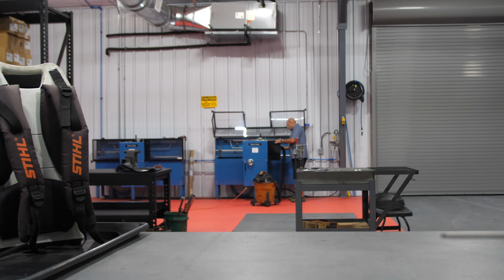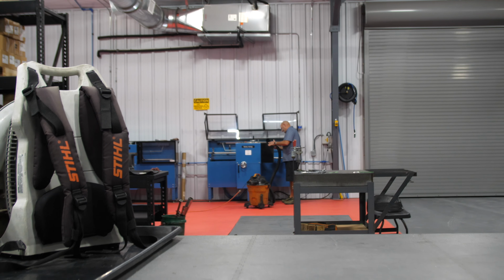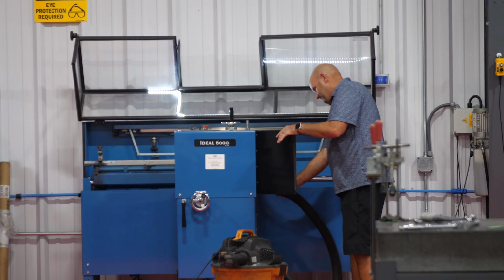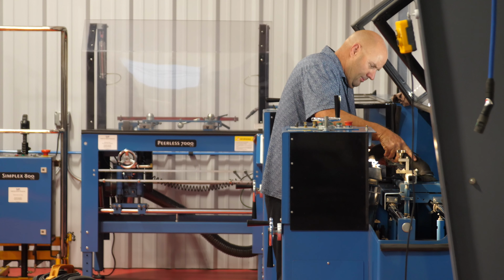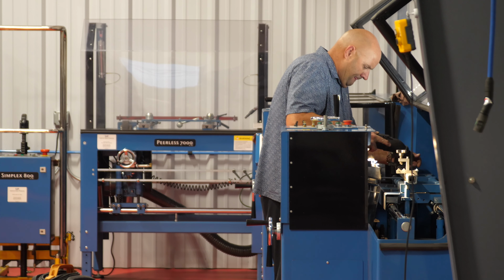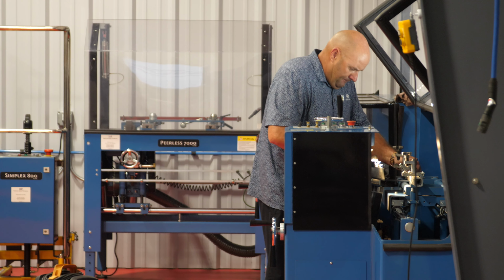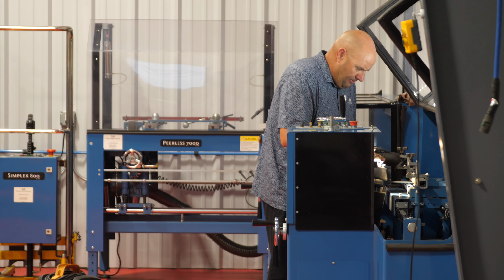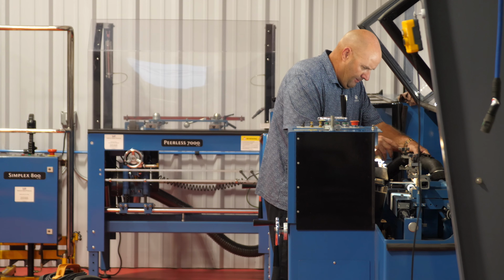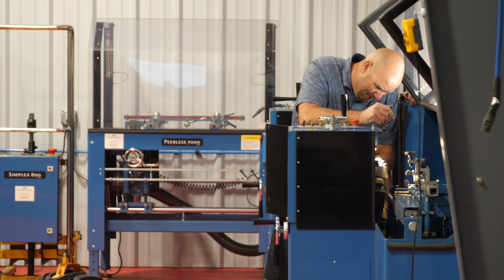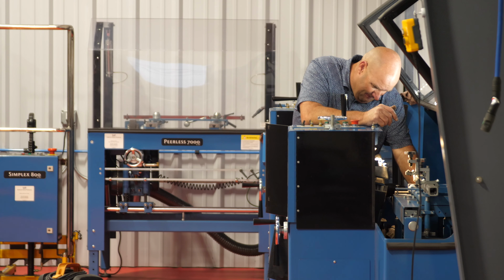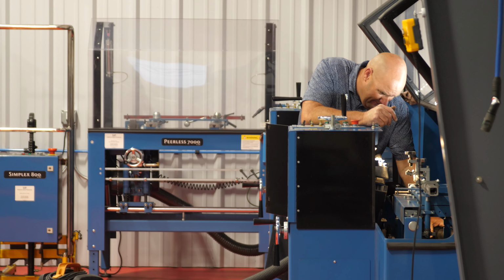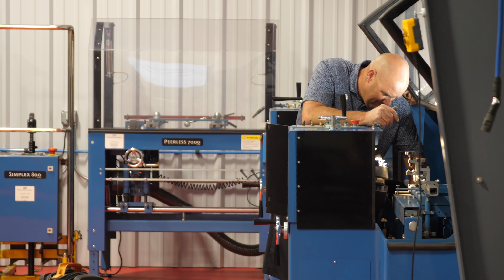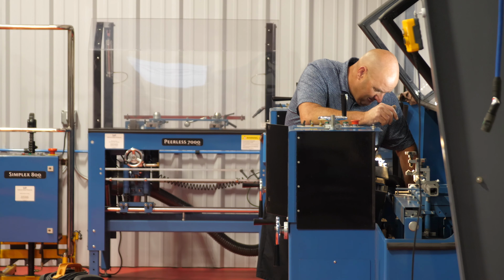You'll use a shop vac with a soft bristle brush on the interior of the grinder. We know lots of you who do it, so I'll address compressed air. We do not recommend it, but you can wear a mask and lightly blow off things like the V support brackets after you've already vacuumed the grinder out. If you're going to use air, we recommend you stay away from moving parts like your carriage bearings. If you aren't careful, you can pop the seals, which will allow grinding dust and dirt to get in.